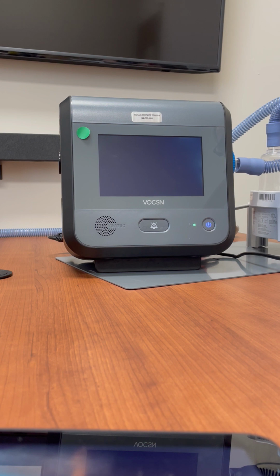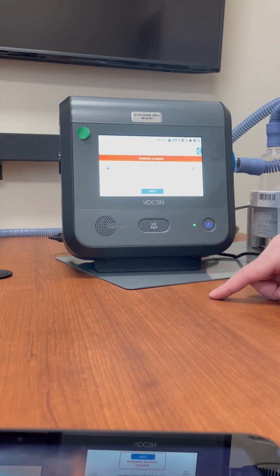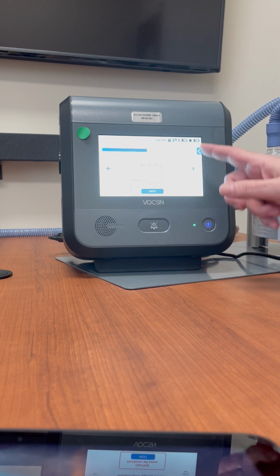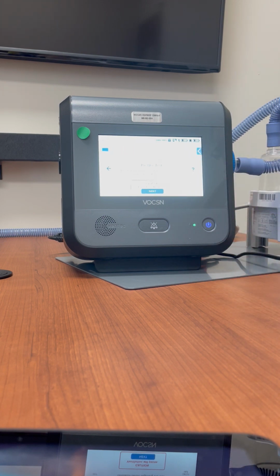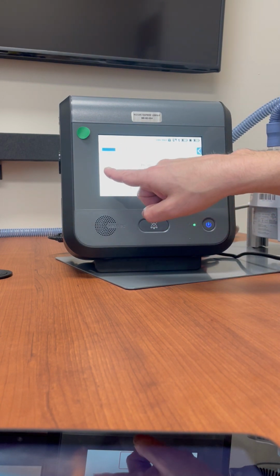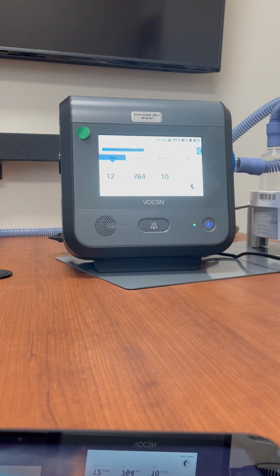There it goes. So it turned green to say we're running. But again, once it senses the batteries, it should turn amber again. Every time the vent powers up, we see this pre-use test, which a respiratory therapist would use when they first connect your ventilator. But again, it comes up every time. So every time you power on first, and then hit the exit arrow on the left-hand side of your screen, which will bring you to the home screen.